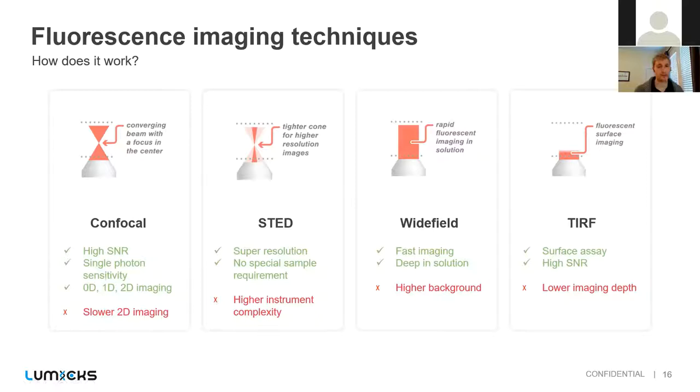Confocal is also diffraction limited. So depending on your wavelength, that can be 200 to 300 nanometers. If you want to break the diffraction limit, you have to use a super resolution technique. We offer STED, which is one form of super resolution that's nice because it doesn't require special sample preparation. However, it is more expensive because it's a more complex instrumentation. And this can get your resolution down to about 35 nanometers.